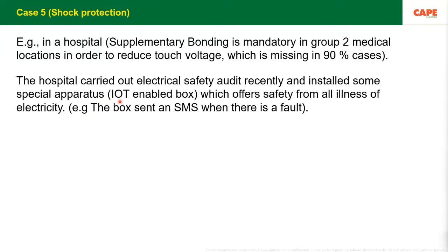I call this a black box. They have a special panel, which the supplier told them is an IoT enabled panel, and that it will offer every kind of safety. One of the safety features they told me about is that the box will send an SMS when there is a fault. That means there is an insulation failure.